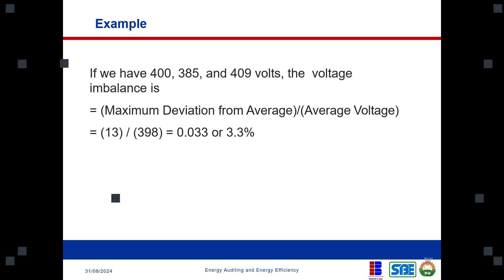Now, the voltage imbalance in this case is the maximum deviation from the average divided by the average voltage. Like we did in the other example, the maximum deviation here is 13. When you run this calculation, you realize that the maximum deviation is 13 and the average is 398. So when we do this calculation, we have 3.3% voltage imbalance.